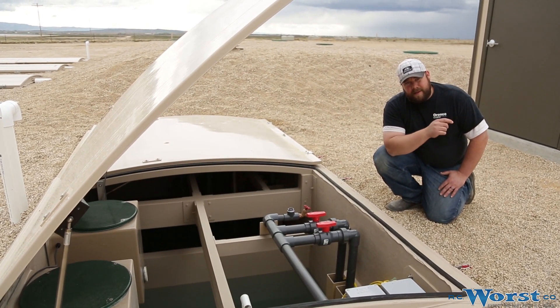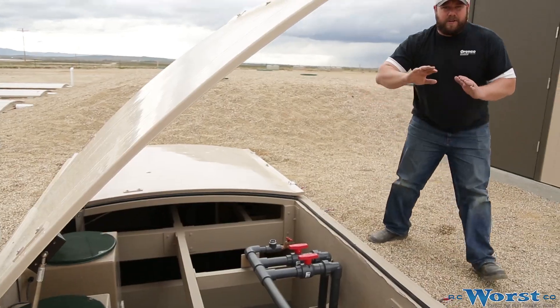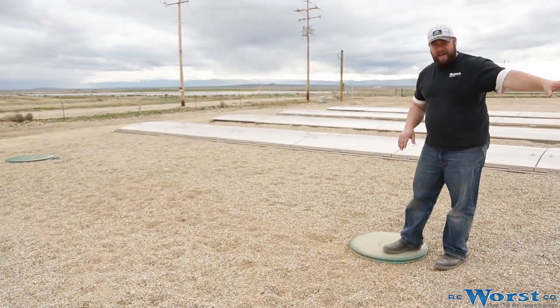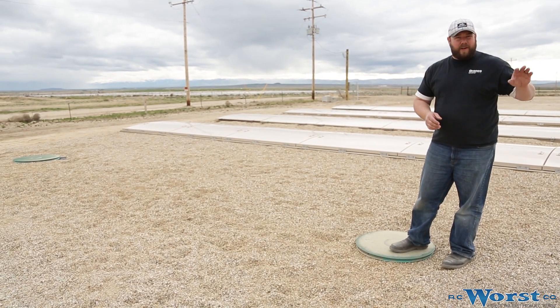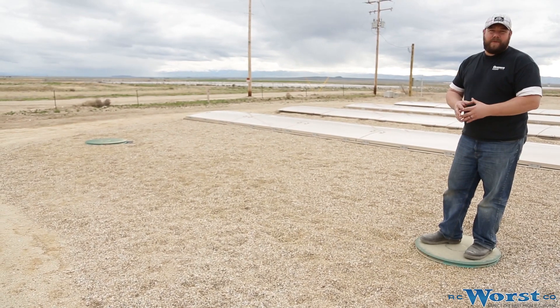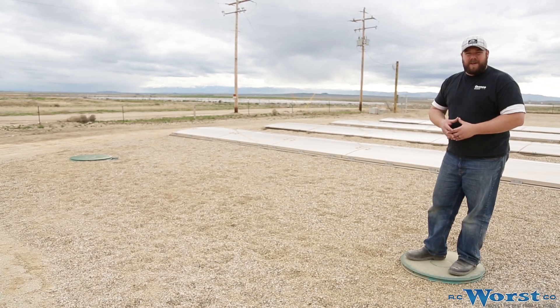They're going to pick up a carbon source, which is probably going to be micro-C. We'll add that into the pressure line and then dose over to this tank here. Right underneath my feet is a 20,000-gallon single-compartment Xerxes tank. The dose pumps pump through our control building, and those peristaltic pumps will inject carbon into that pressure line so that through this post-anoxic reactor, the carbon will react with the remaining nitrate, allowing us to achieve that 19 total nitrogen compliance limit.